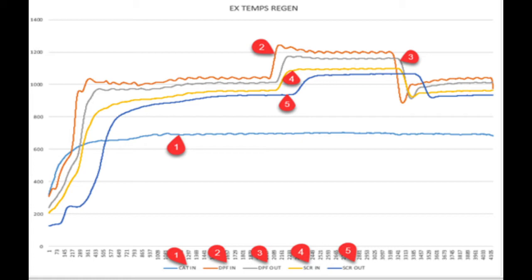So what are we looking at? Number one is the temperature coming out of the turbo, going into the after-treatment housing in front of the catalyst. Number two is the temperature coming out of the other side of the catalyst. Number three is the temperature coming out of the outside of the filter. Number four is the inlet to the SCR brick. And number five is the outlet from the SCR brick. After it leaves there, it goes out the stacks.